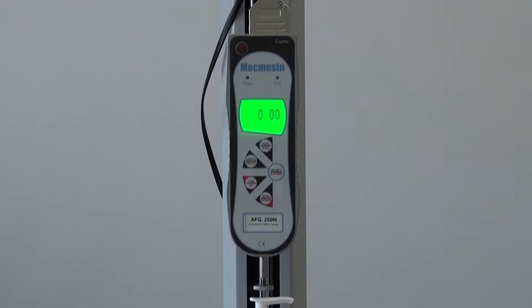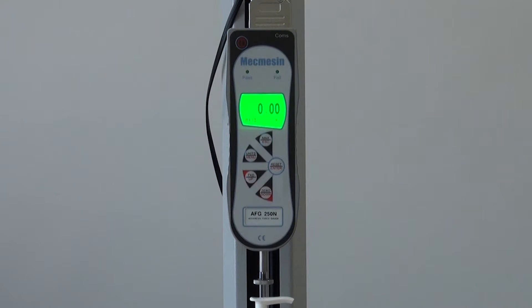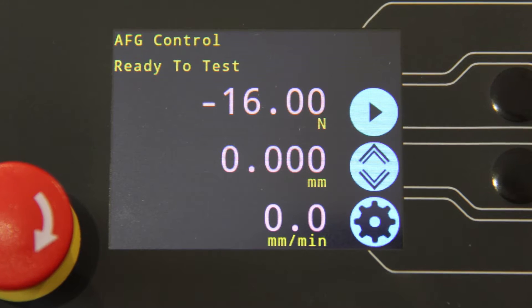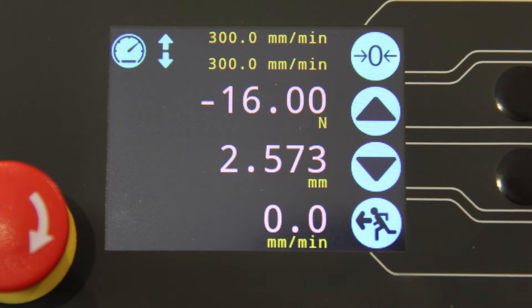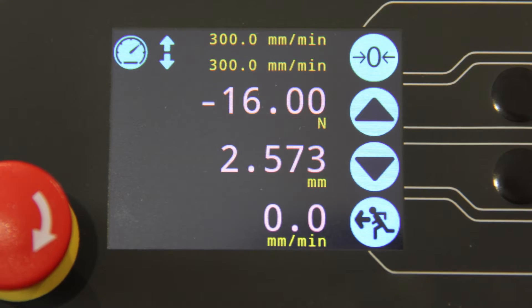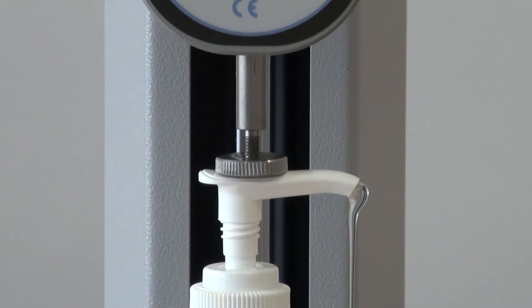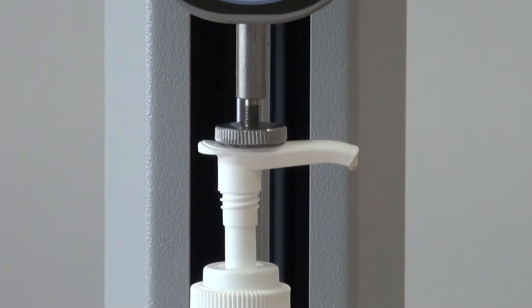When using the Mecmesin advanced force gauge, it is also possible to use AFG control. In this option, you can use the signal of the advanced force gauge to stop, or stop and reverse the cross head based on either a force value or a point of collapse. Very handy for tensile testing or top load testing of plastic bottles to reverse the cross head as soon as the sample has broken or collapsed.